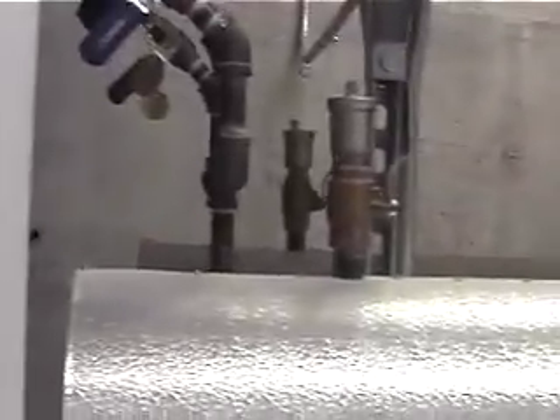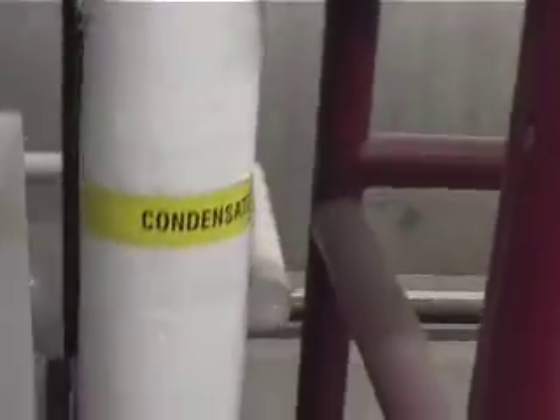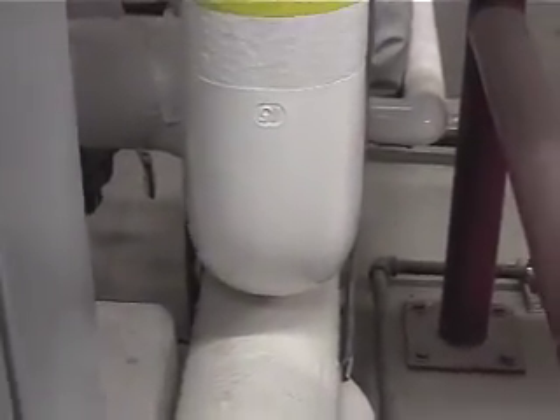Okay. Other than that, the system looks pretty good. Now, again, we have air breathers on them. Air vents, yeah. You've got some getting rid of the air and the non-condensables. I'm glad to see that. There are also vacuum breakers integral with the steam traps down here. So when these valves modulate back and you get a vacuum in here, you wouldn't be able to drain it. So that breaks the vacuum, and you get gravity drainage back into your receiver tank. So everything looks good.